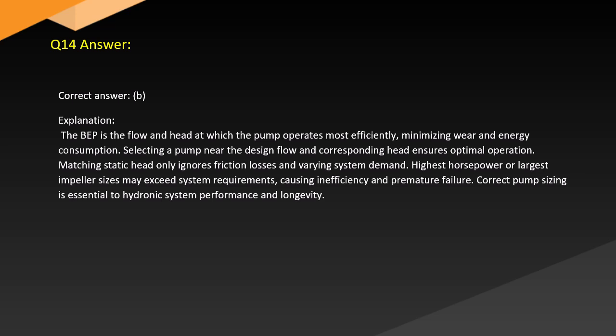Answer. Correct answer, B. Explanation. The BEP is the flow and head at which the pump operates most efficiently, minimizing wear and energy consumption. Selecting a pump near the design flow and corresponding head ensures optimal operation. Matching static head only ignores friction losses and varying system demand. Highest horsepower or largest impeller sizes may exceed system requirements, causing inefficiency and premature failure. Correct pump size is essential to hydronic system performance and longevity.